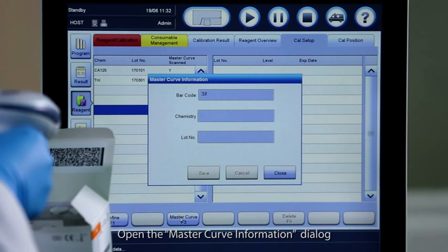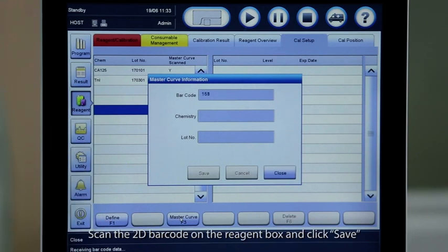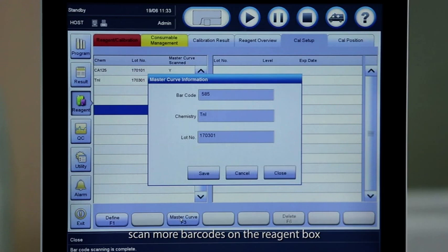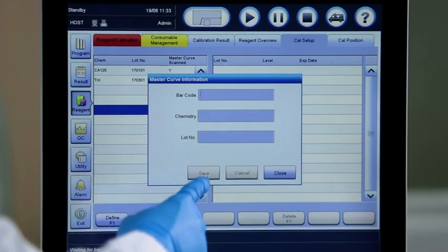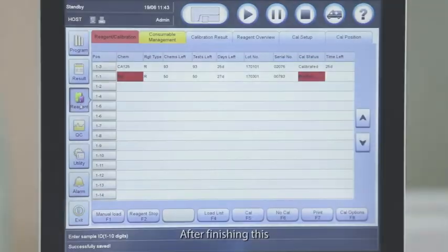Next step is to import master curve information. Open the master curve information dialog. Scan the 2D barcode on the reagent box and click save. To define more master curves, scan more barcodes on the reagent box.